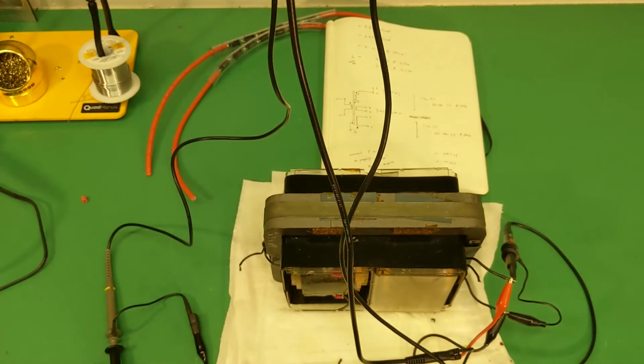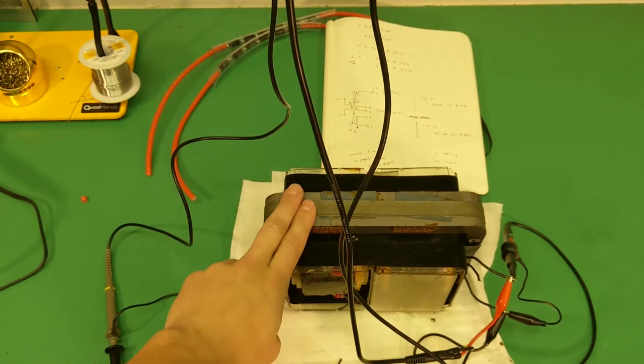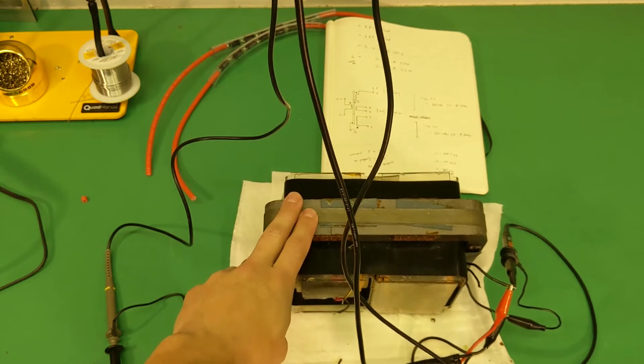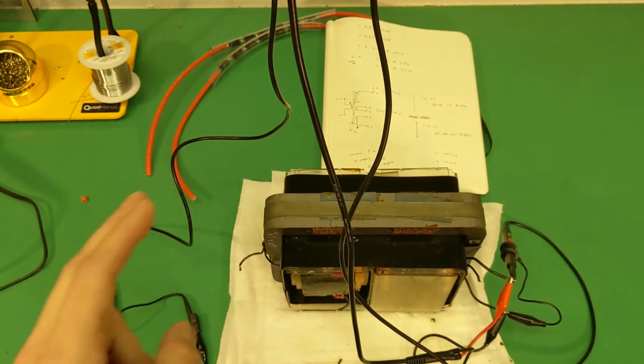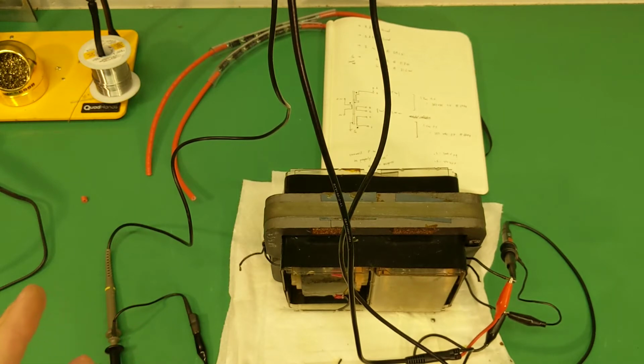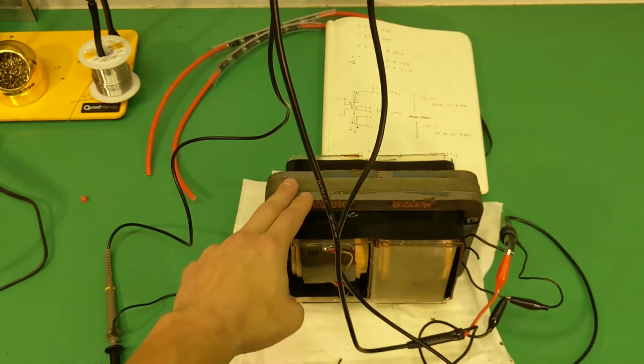In part 2, we'll verify the internal wiring of this transformer by injecting a small signal and measuring the output voltages through transformer action, viewing them on the oscilloscope to confirm proper operation, ratios, and phasing.